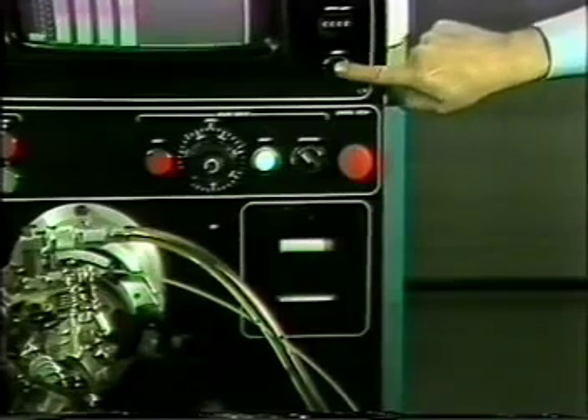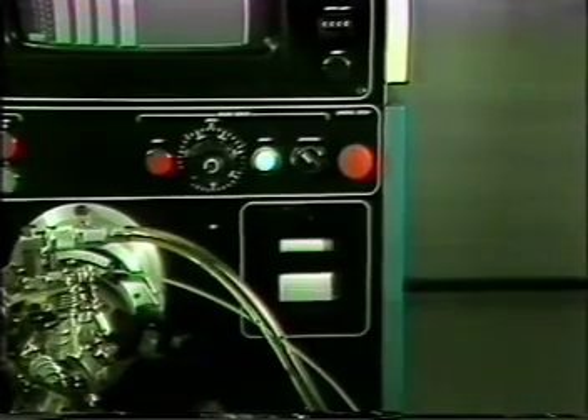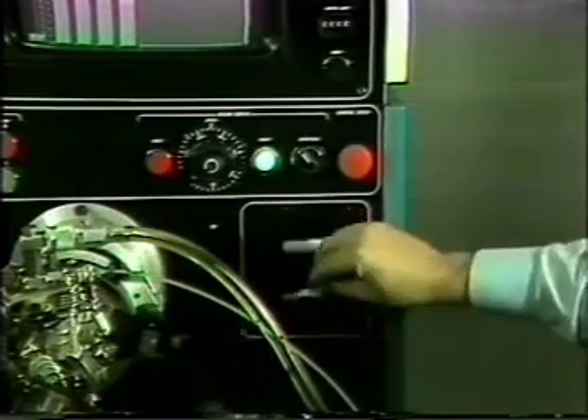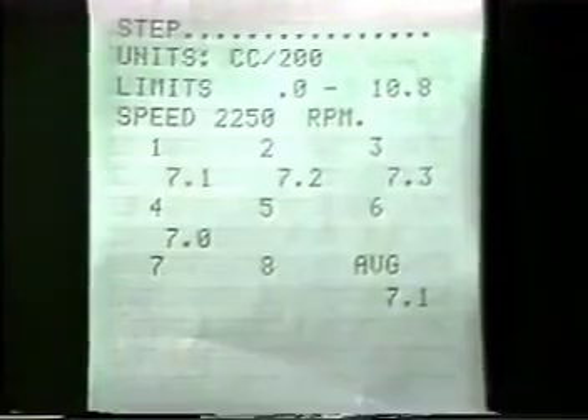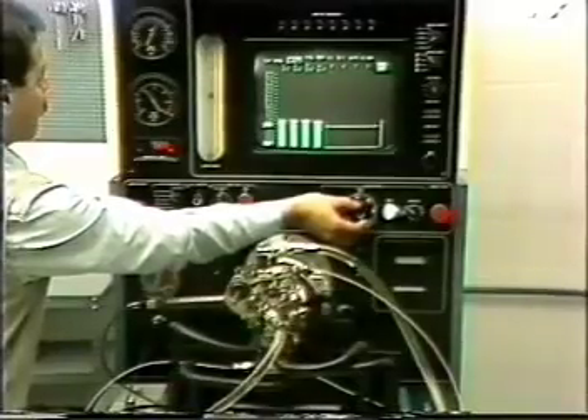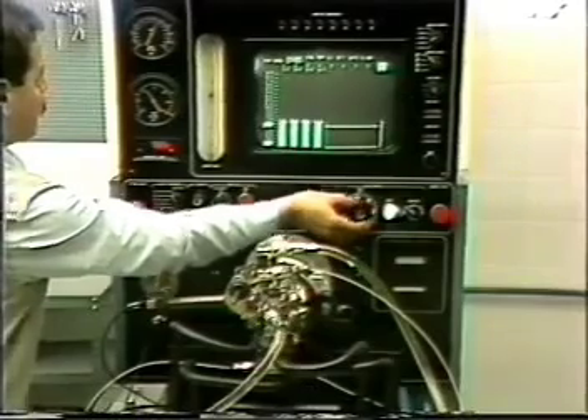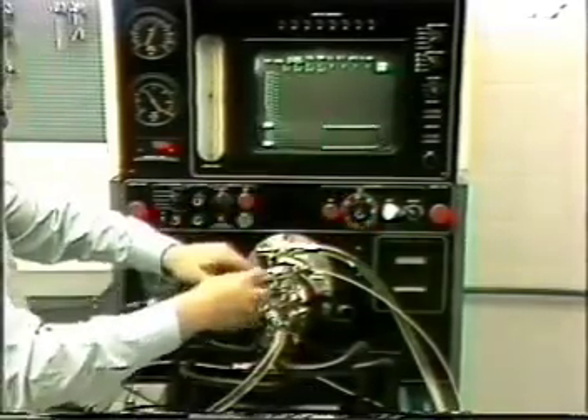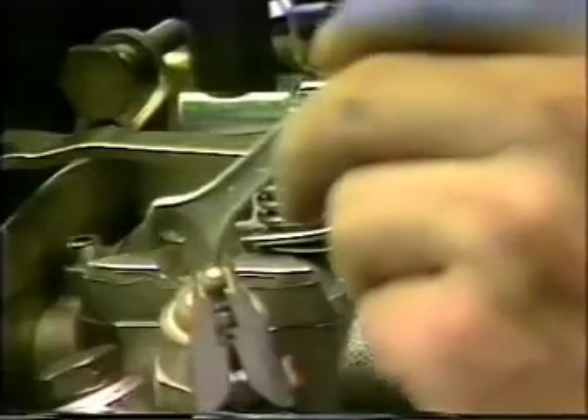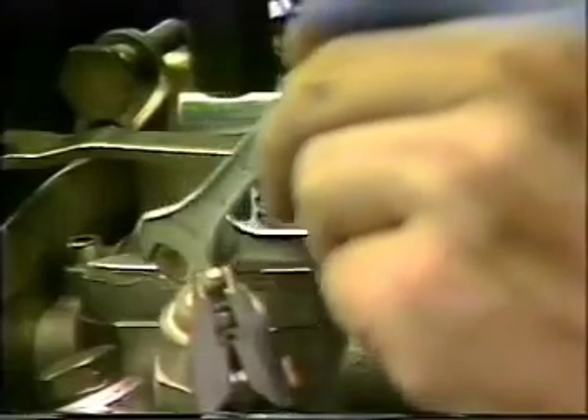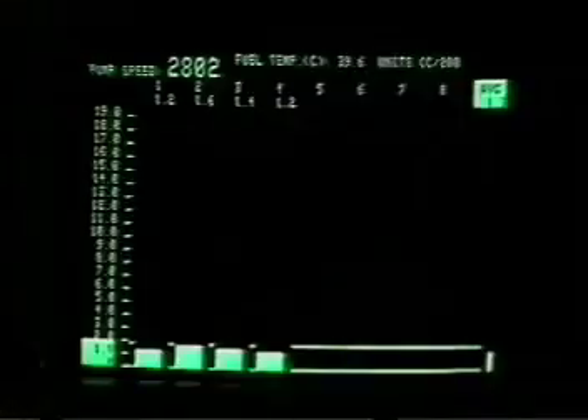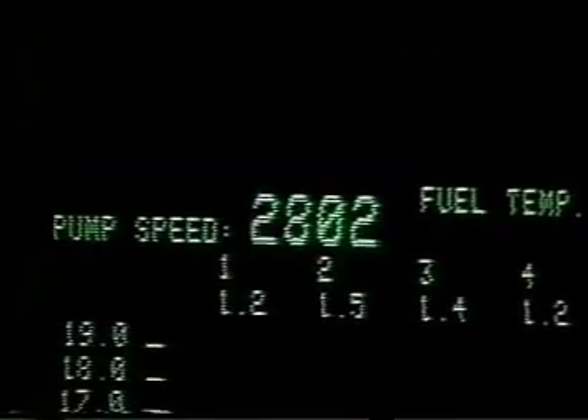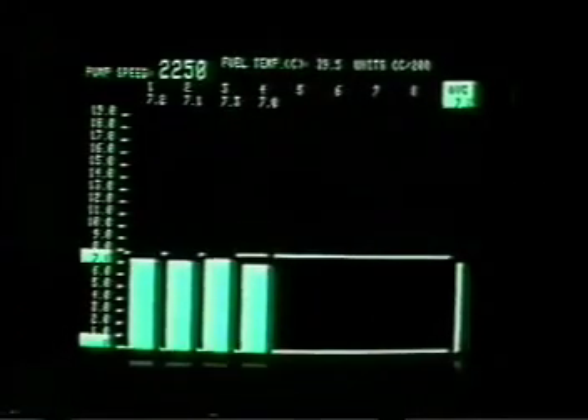Begin the regulator tests. With the throttle lever at maximum, note the flow delivered by the pump. Now adjust the regulator by setting the bench speed to the indicated value. Move the throttle lever until you achieve the flow reflected in the test data. Next, lock the maximum speed screw and verify the flow again. Now check the total cutoff of the regulator. Now you should observe if the regulator recovers when the revolutions drop to those established in the test data.